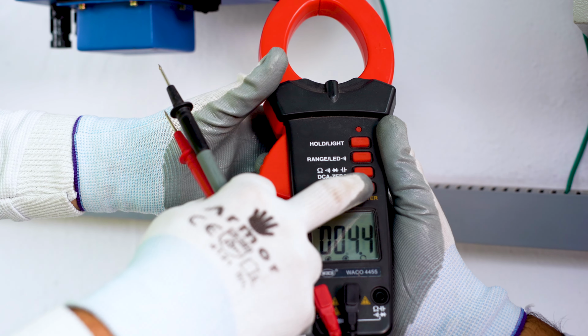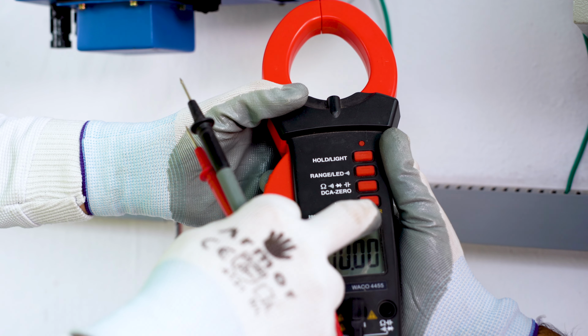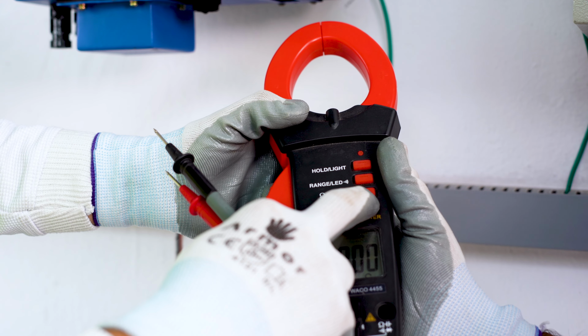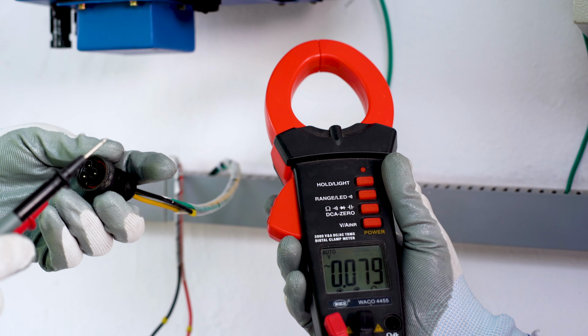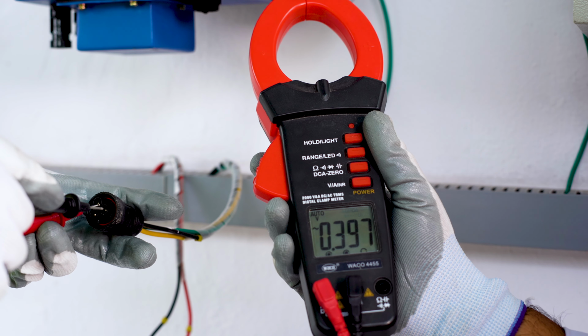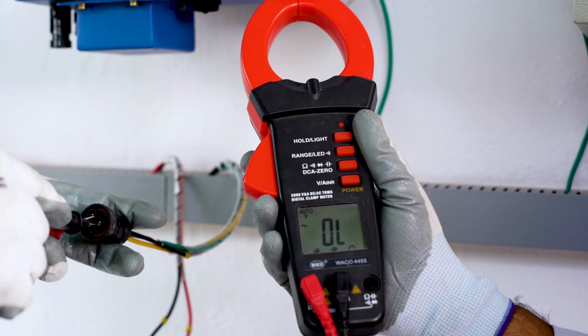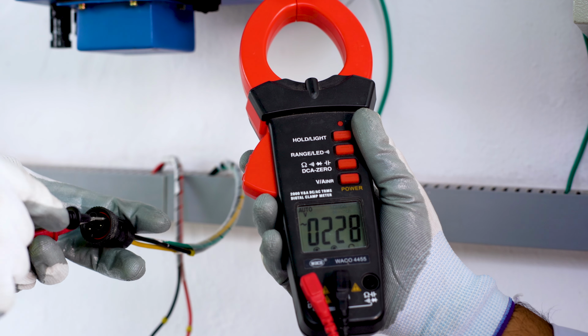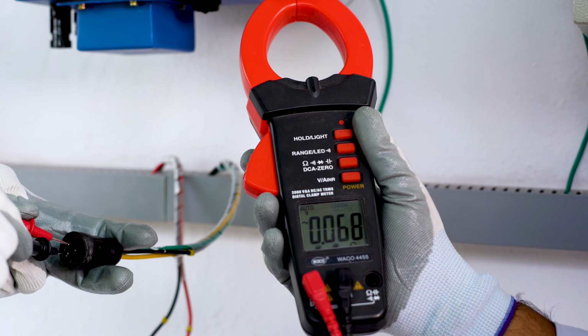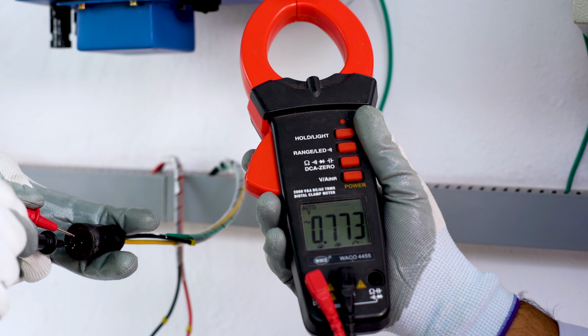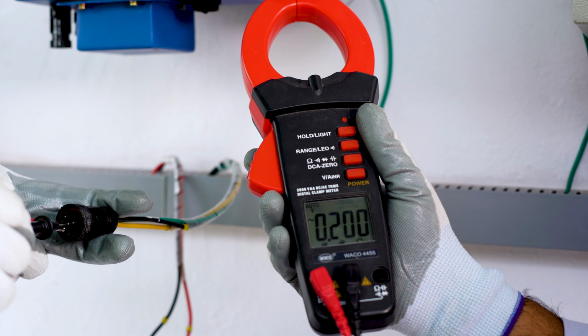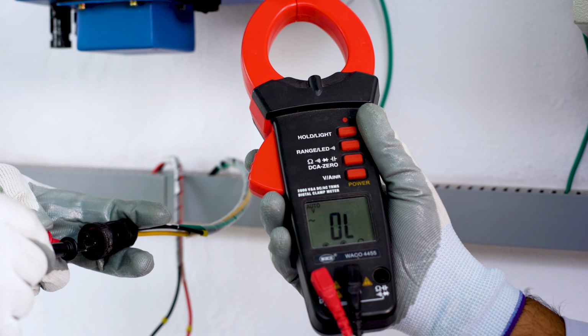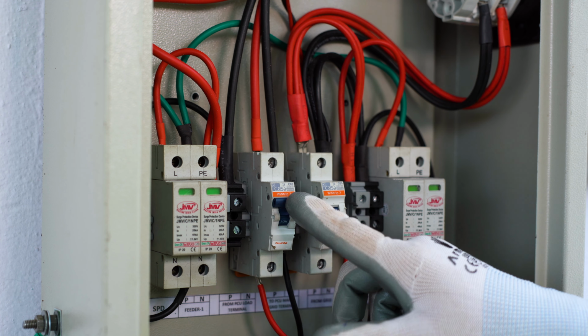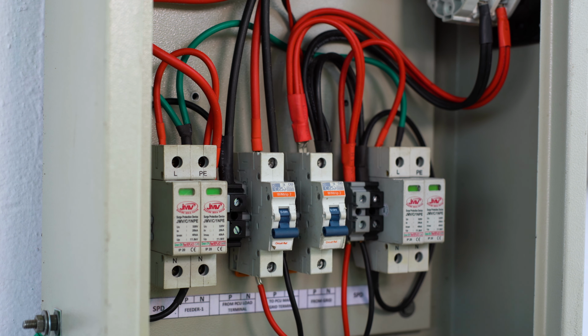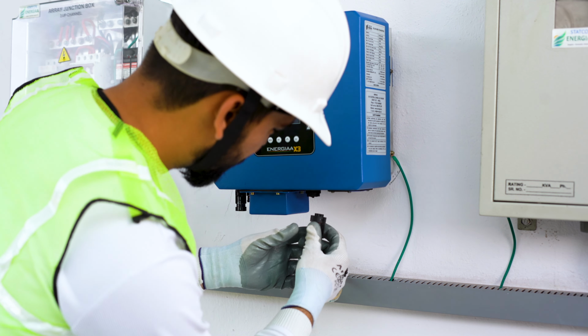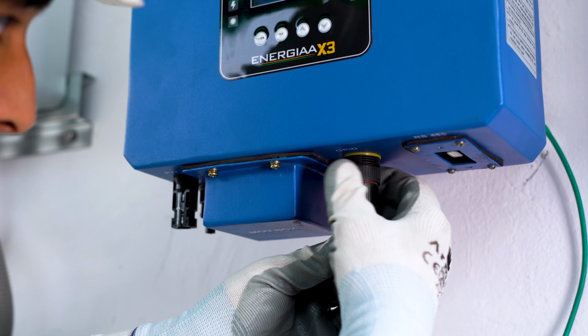To check the grid AC voltage, select the AC mode on the multimeter. Put the probes in the AC connector and check the voltage on the multimeter. To connect the AC connector, first switch off the MCB in the ACDB. Then connect the AC connector to the inverter. Ensure it is properly tightened.